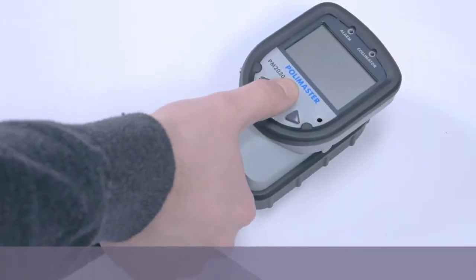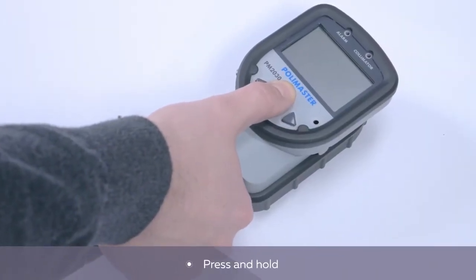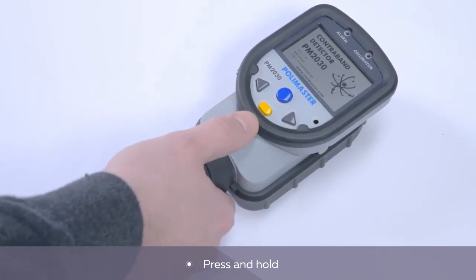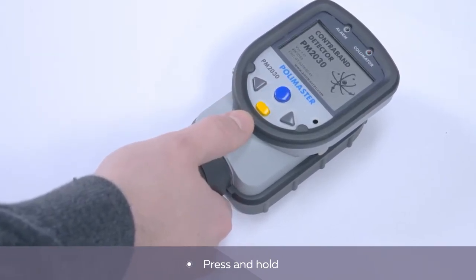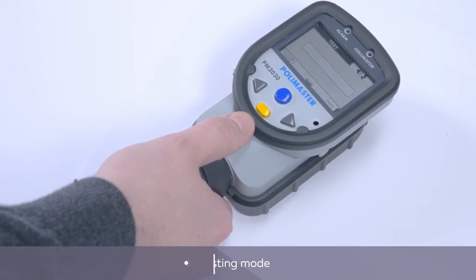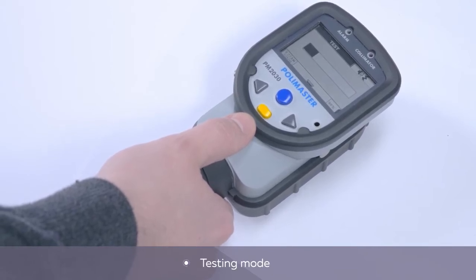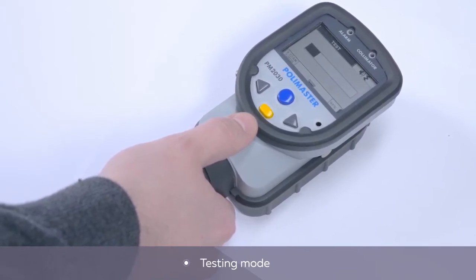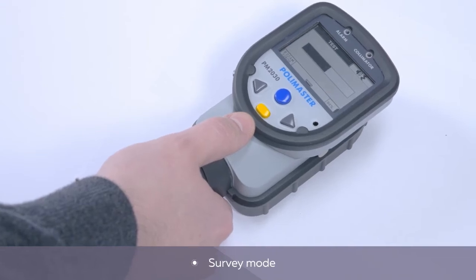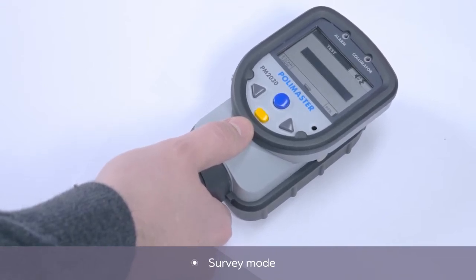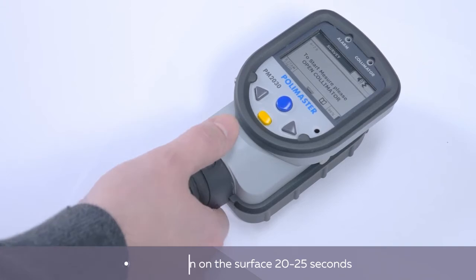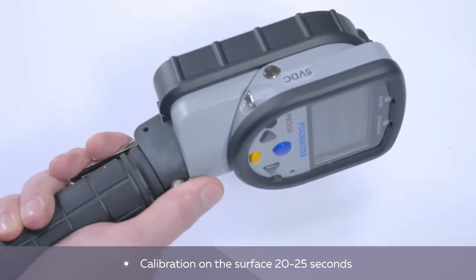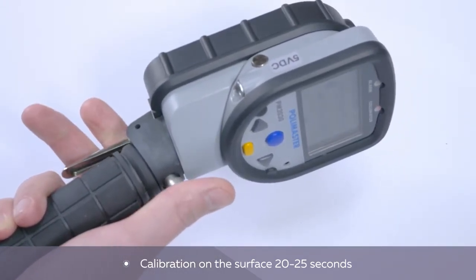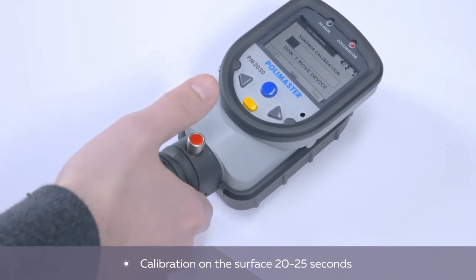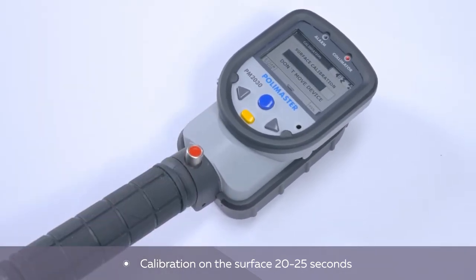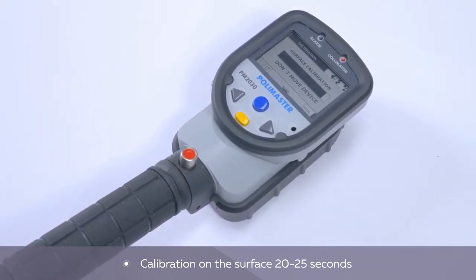To turn the device on, press and hold the Select button until the name of the device appears on the screen. The PM2030 automatically enters the testing mode, and the visual alarm and collimator indicators are activated. If the handle vibrates, the survey mode is switched on. Put the instrument to the inspected object. Now we can calibrate the instrument on the surface. For this purpose, we press and fix the lever with a pin to open the collimator. After the calibration is fulfilled in 20 to 25 seconds, we can proceed to the inspection.